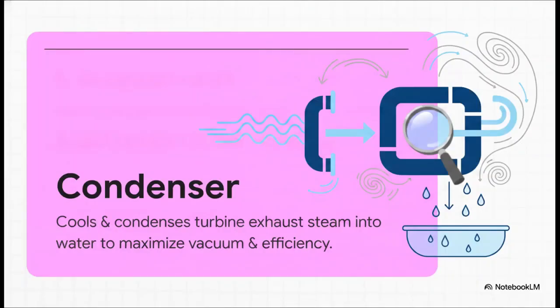Before we get buried in the data, let's do a quick primer on how a condenser actually works in a power plant, especially for any junior team members tuning in. Think of a condenser as a massive, absolutely critical heat exchanger. It's physically connected directly to the exhaust of the low-pressure, or LP, turbine. Its one and only job is to take the spent exhaust steam leaving that turbine, cool it down really rapidly, and condense it back into liquid water. But why? Because condensing that steam shrinks its volume so drastically that it creates an incredibly powerful vacuum. That vacuum literally pulls the steam through the turbine blades, which maximizes the mechanical work we can extract from it. Without a strong vacuum right there, the whole plant's efficiency just totally tanks.